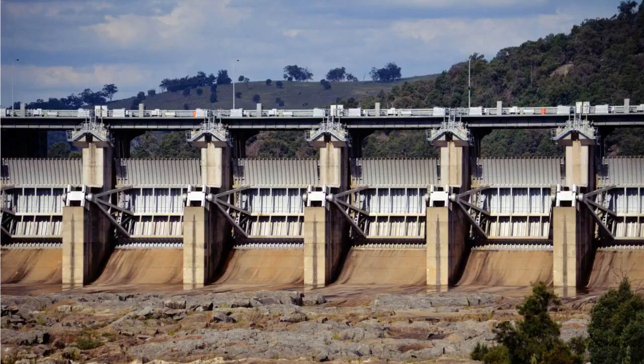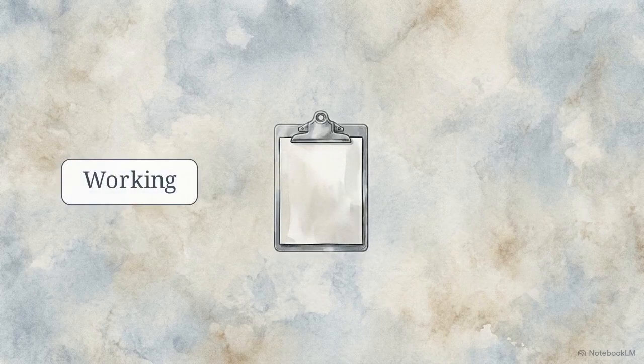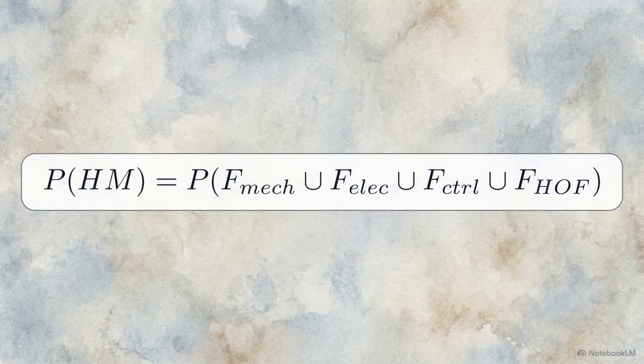Structural robustness fails to prevent catastrophe when the gates meant to modulate the flow remain frozen in place during a surge, forcing the reservoir into a state of overtopping. The actual bottleneck in these catastrophic events lies in the hydromechanical, or HM, systems, specifically the failure of spillway gates to actuate under load. Traditionally, dam safety audits evaluate these complex mechanisms as binary states, assuming they either work perfectly or they do not. This simplification breaks down in high-stress, compound hazard environments.